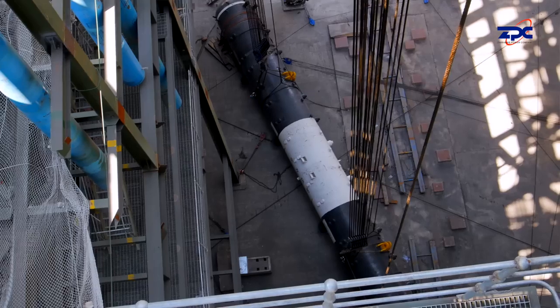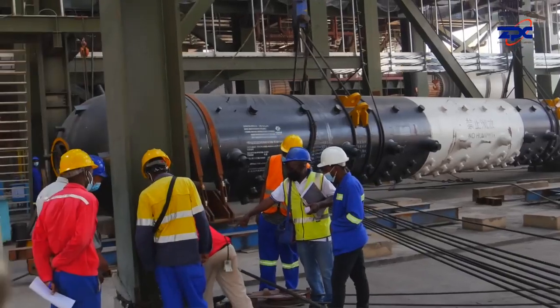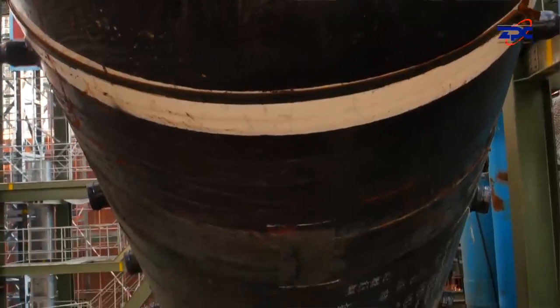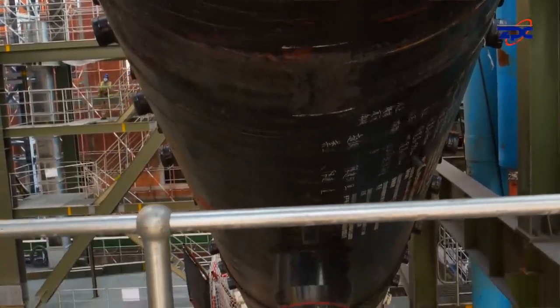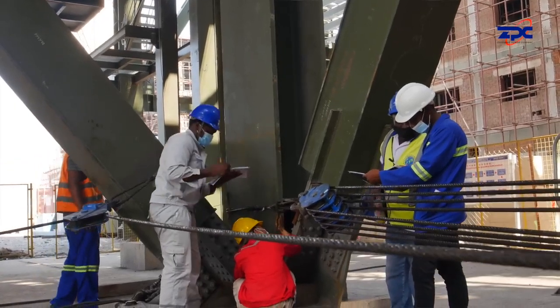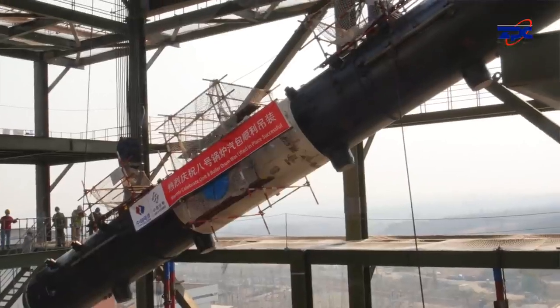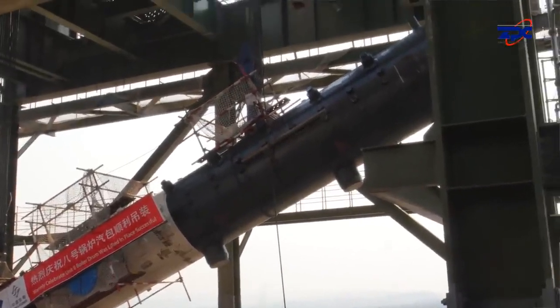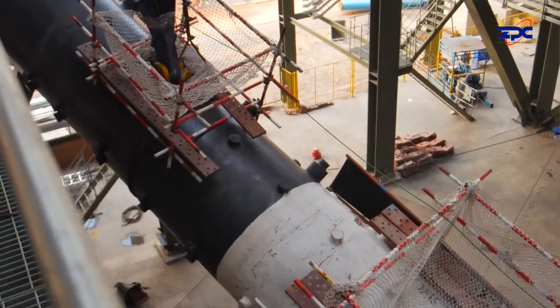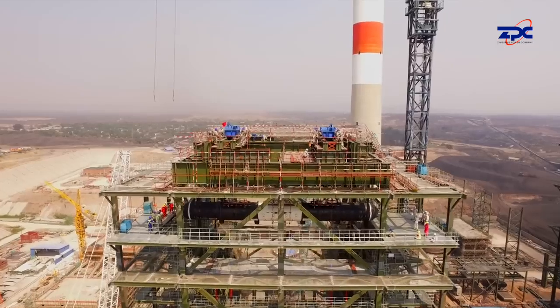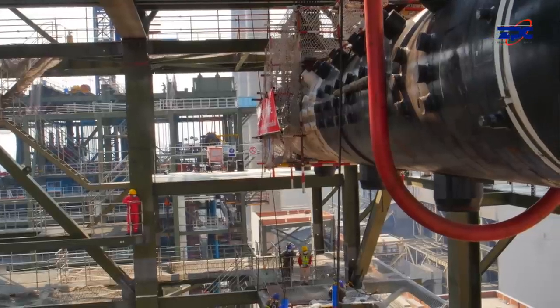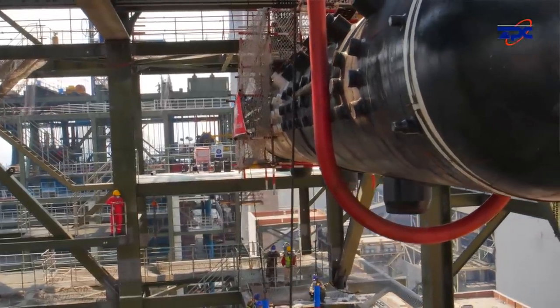Now, the boiler is a critical component of the power plant because it is the component that generates steam. This steam will then later be used to turn the turbine and in turn the electric generator that will produce electricity for transmission to the grid. So the boiler at Hwange Expansion Project is a 335 megawatt subcritical boiler with a rated steam output of 1,110 tons per hour at boiler maximum continuous rating. The height of the roof is 75.4 meters and our rated steam output is at a temperature of 541 degrees Celsius and a pressure of 17.4 megapascals.